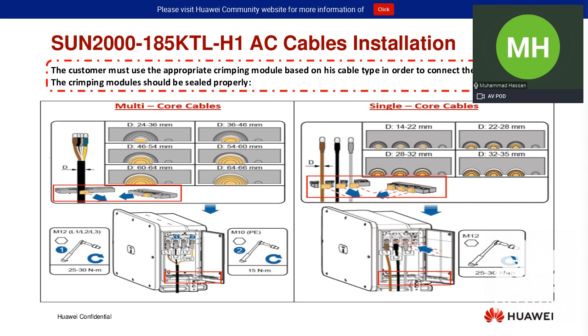We are also providing the gland for the single core cables. You take out the rubbers to make space for the three cables, and then you fix the AC cable glands to seal the compartment. If you don't seal that compartment correctly, then water can go inside and damage that inverter, and there will be a problem for the production of that one.